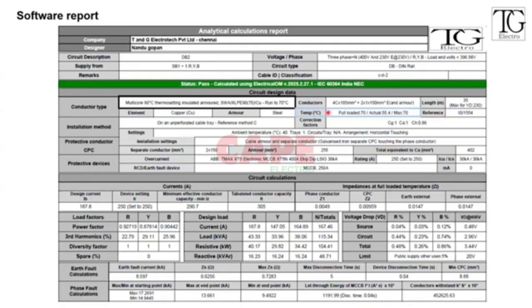Suppose here the temperature at this value is actually 55 degrees. So maybe in future, if you feel that the temperature has increased, then you can check the connections for loose connections, or whether there is some overload, and you can get the actual temperature rise. You can get what correction factors you have used and what ambient temperature of the surroundings was used. You will also get the Z percentage, the percentage impedance of the source, the design current, and the device tripping current.